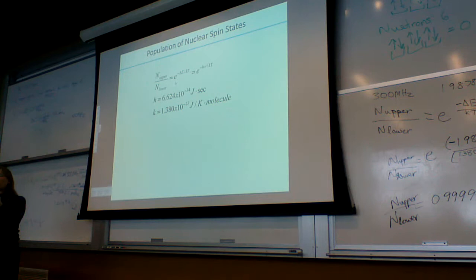And what that does is it saturates out the signal and it disappears from the spectrum, which is helpful when we're trying to get rid of a water signal, but not so helpful if you just saturate all your signals out. So you gotta be careful with how much energy you give to the system or you're gonna get them saturated. Now the NMR actually does all that for you and calculates the energy. You're not gonna be messing with those things. But I want you to know that that is a potential problem, that you can saturate out that signal.